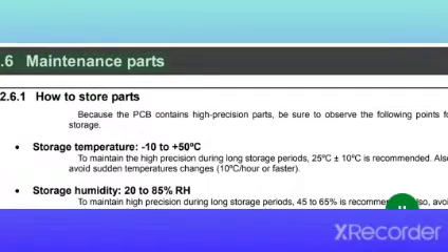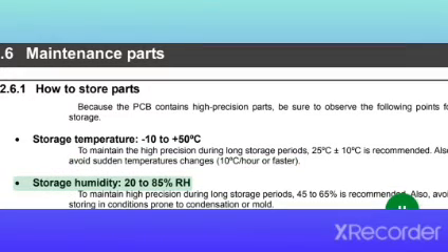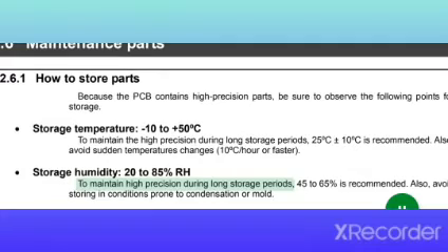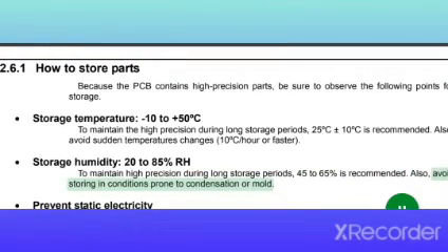2.6 Maintenance parts, 2 to 30. 2.6.1 How to store parts. Because the PCB contains high precision parts, be sure to observe the following points for storage. Storage temperature: -10 to +50 C. To maintain the high precision during long storage periods, 25 C ±10 C is recommended. Also, avoid sudden temperature changes of 10 C/hour or faster. Storage humidity: 20 to 85%. To maintain high precision during long storage periods, 45 to 65% is recommended. Also, avoid storing in conditions prone to condensation or mold.